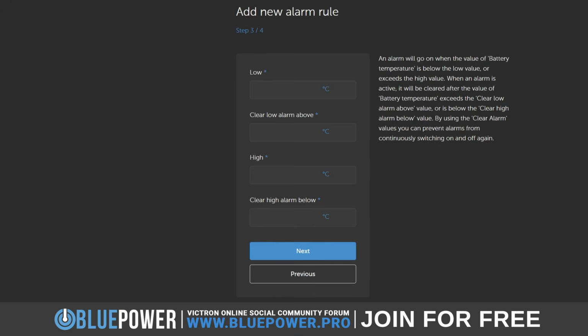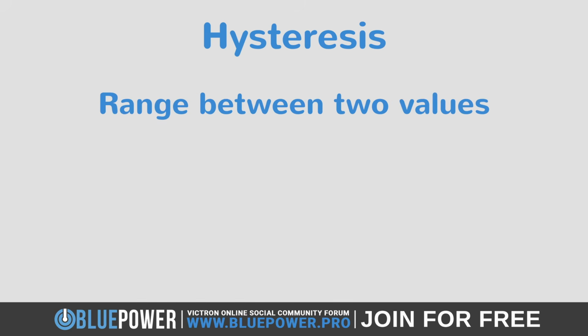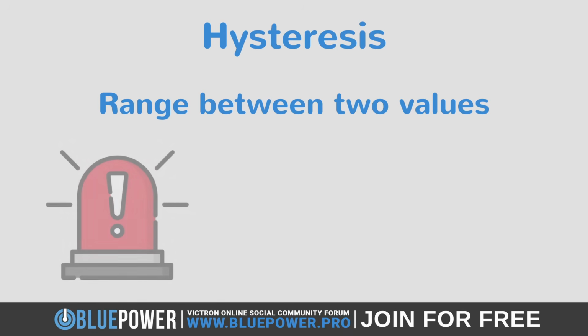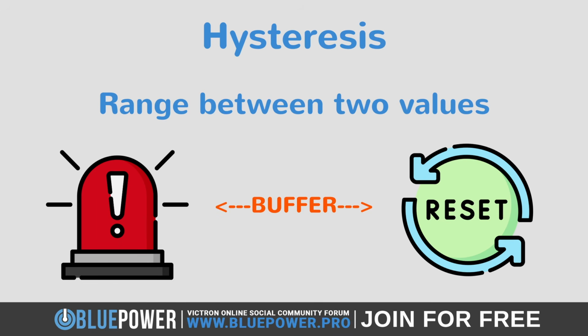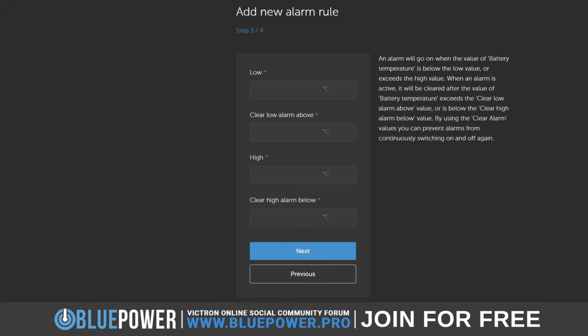Now, we get to the most difficult part of this process, which is to understand how to set the high and low values in order to create their hysteresis. Hysteresis defines the buffer or range that a parameter must move through before an alarm resets. This buffer ensures that the alarm is not cleared immediately if the parameter fluctuates slightly above or below the threshold, thus preventing nuisance alarms. With that in mind, let's begin by entering the low value.